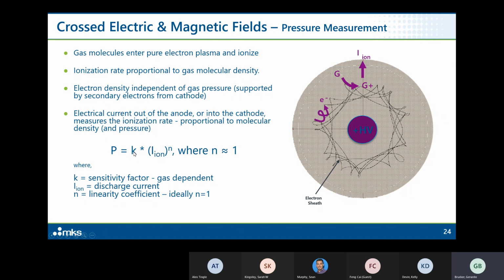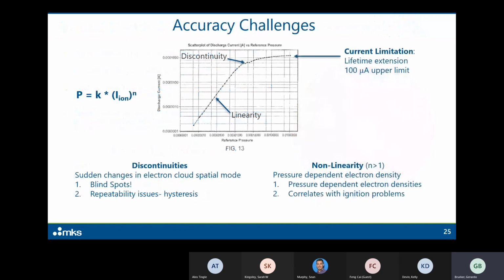And K here is the sensitivity factor, I ion is the discharge current, which you measure with an electrometer, and N is the linearity of the device, which you want to be as close to 1 as possible. If it's close to 1, you know that your electron density is independent of pressure, and you get a much better calibration out of this device.